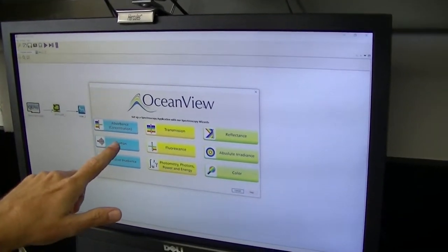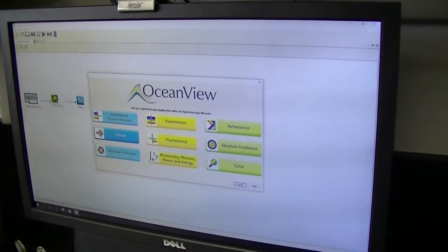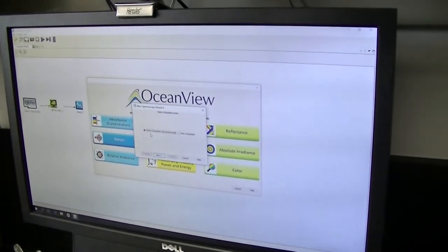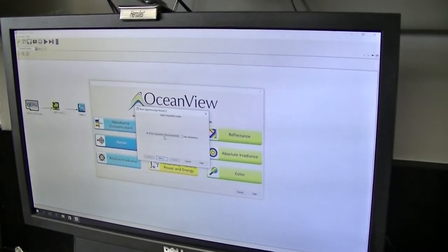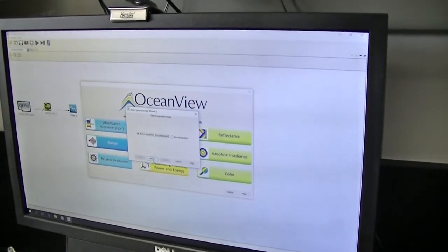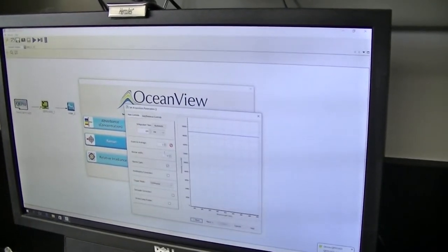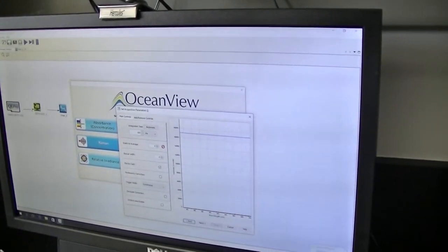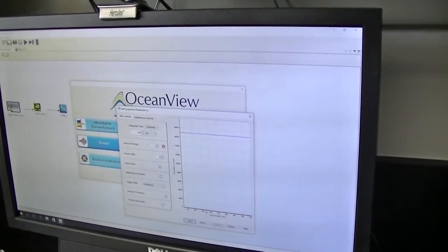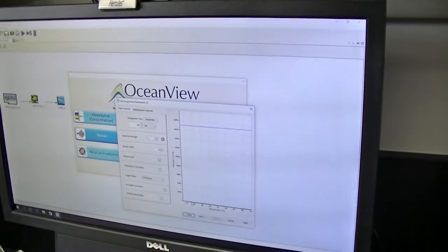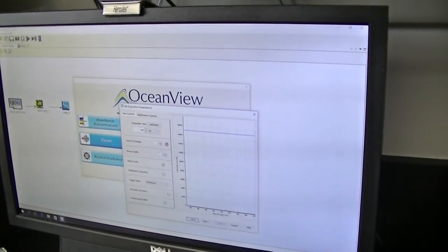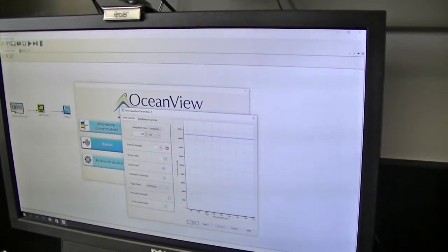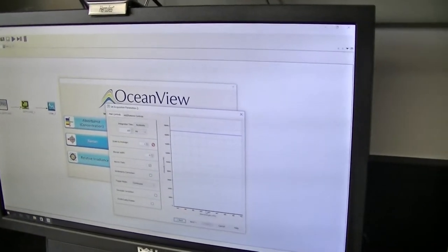But we have the Raman option, so we're going to select that, click it once. It asks if we use the active acquisition that we're collecting now, and that's what we want, so we hit next. So notice we don't have any signal here, so we want to put in a sample. I use acetonitrile almost always, but we can use any of the samples for today. Let's put benzene in here.